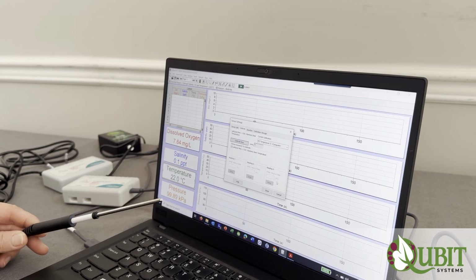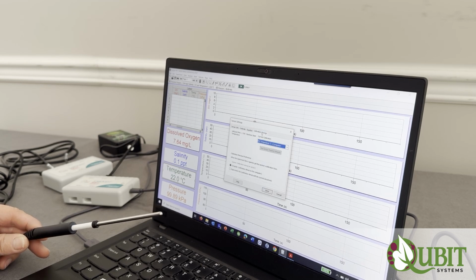I don't have different temperature samples here to demonstrate the process, but the process is the same. The only difference is that with the temperature calibration, the storage of the calibration is not on the sensor. The storage of calibration should be selected for experimental file. And once the temperature sensor has been calibrated, the experimental file that is used to do the calibration should be saved under a new name.